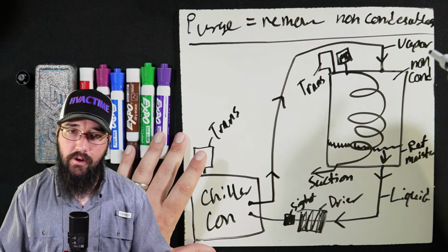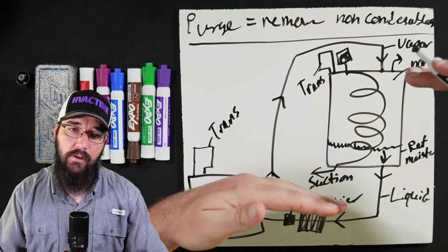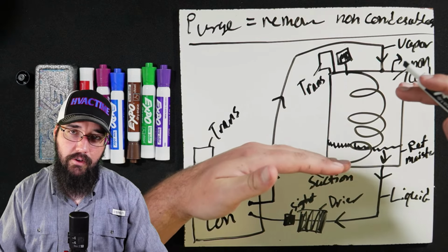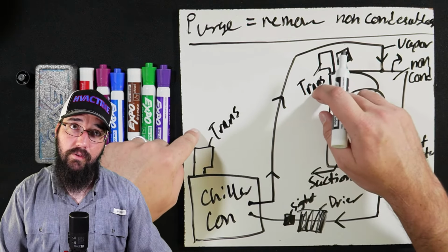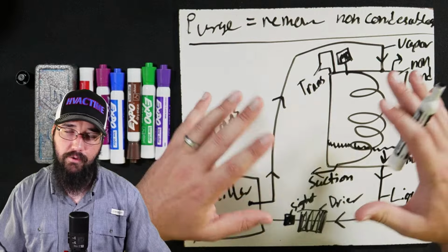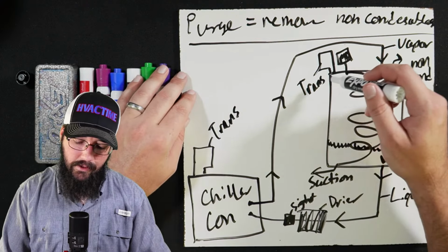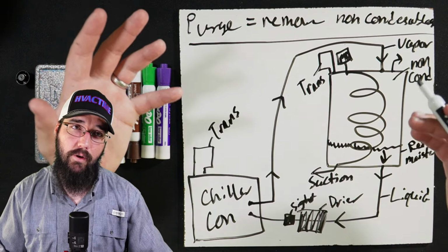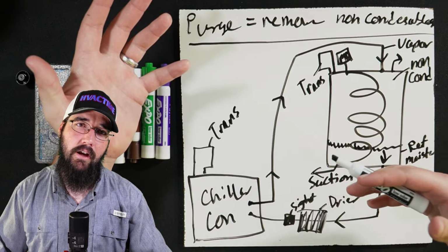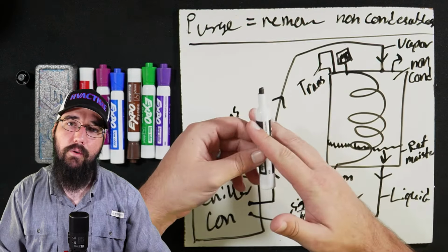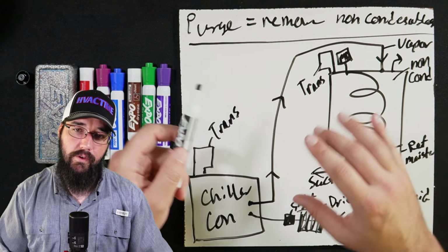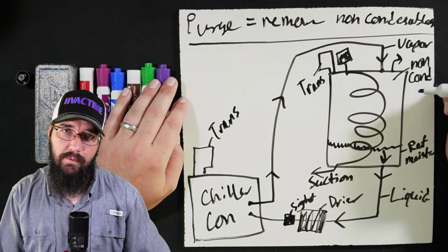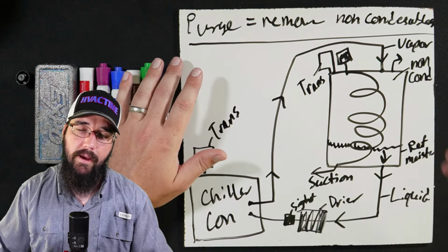going to our pump, and that solenoid valve opens, our pump out pump engages and starts drawing off these pressures. Once it initiates and reaches over the start pump out threshold, it will continue that pump out cycle until these transducers show below the stop pump out threshold, which I don't remember exactly what it is. It's either that or it looks at a period of time. I think York has it either going to pump out for X amount of time, or it's going to show equalized pressures between the two. So once it does that, then it kicks out of pump out, and everything goes back to normal purge operation.